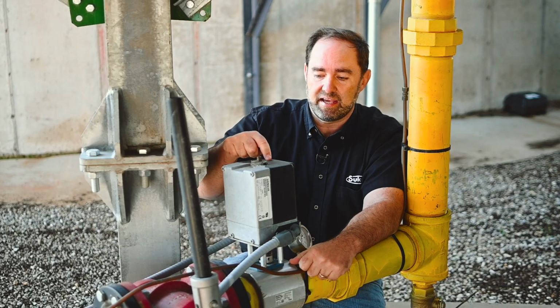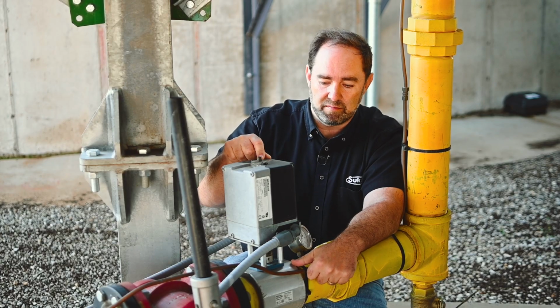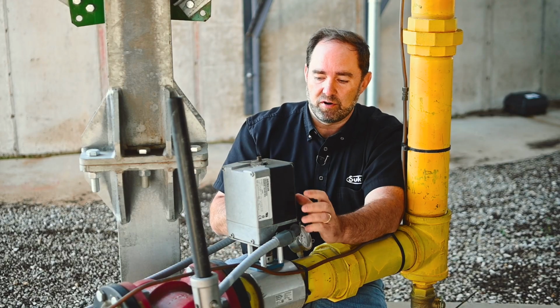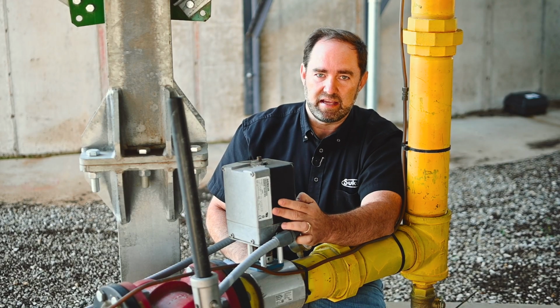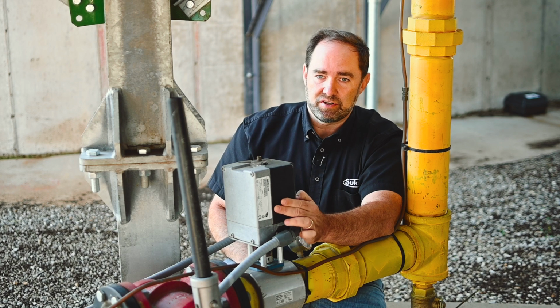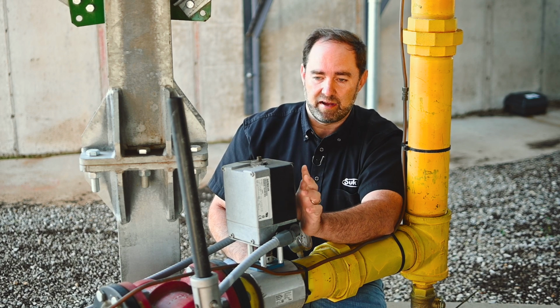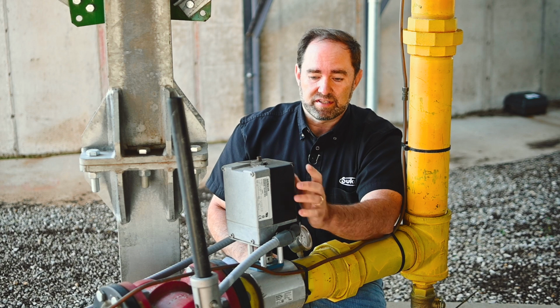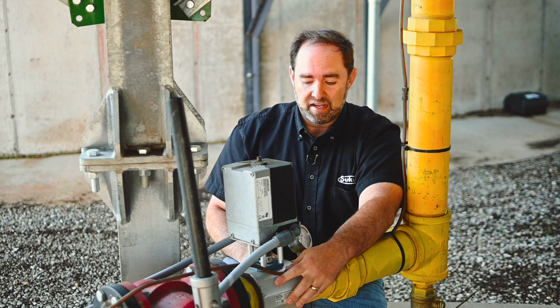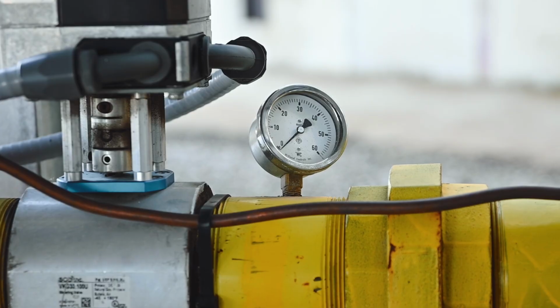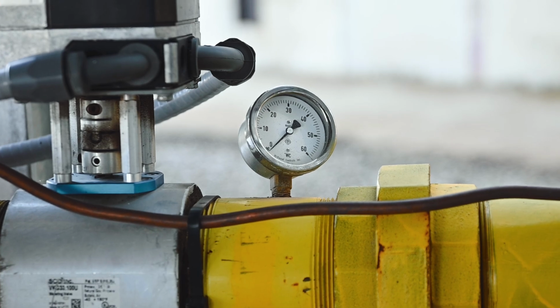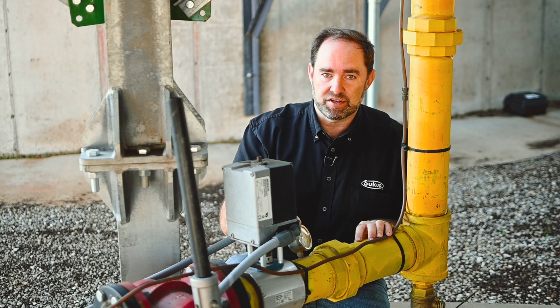There's also another indicator on the top of the actuator motor, and you can take this cover off. If you suspect there's a problem with the motor, the cover will come off, and there's actually a manual and automatic. You can turn it to manual and manually open and close that valve just to make sure that the motor works and that the valve is free and turns. The next thing you've got is another pressure gauge. Now this one is in inches of water column, so this is the control pressure downstream.